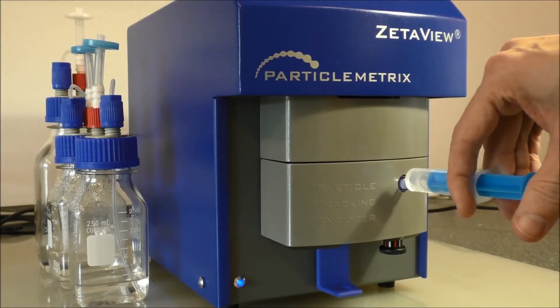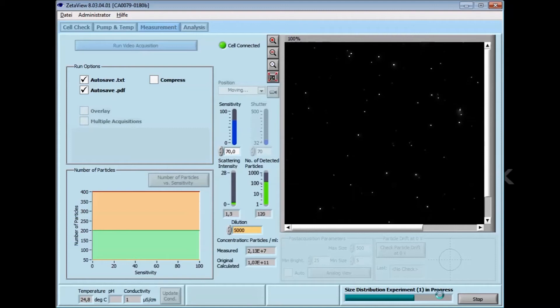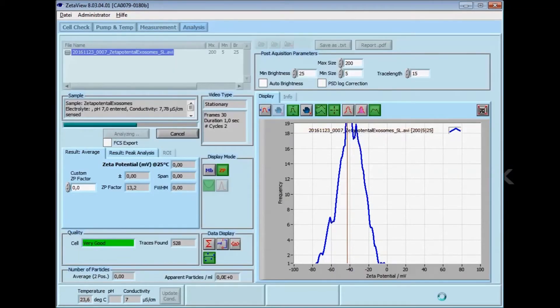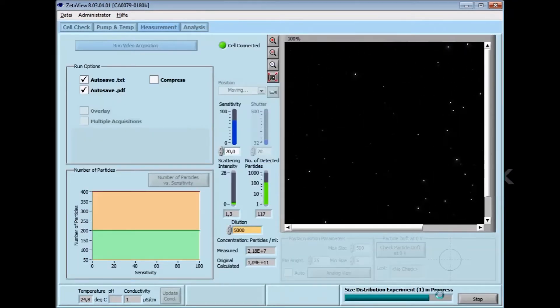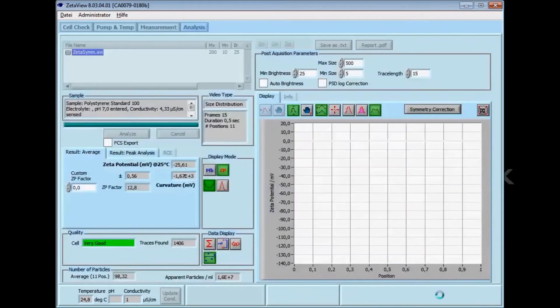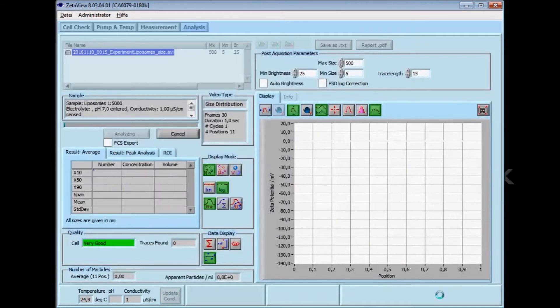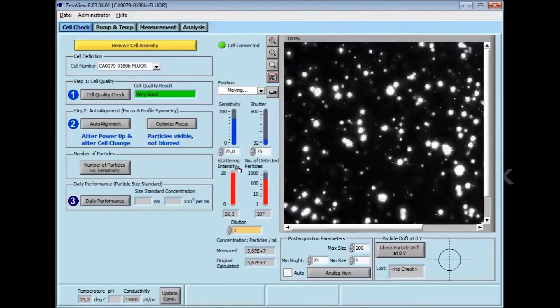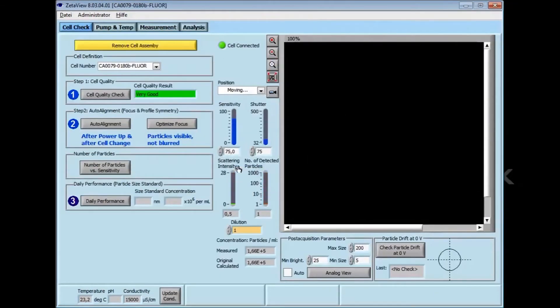The ZetaView is a next-generation nanoparticle tracking analyzer that measures hydrodynamic particle size, zeta potential, and concentration through the analysis of a video sequence at 11 separate positions in the flow cell. Each individual particle in the three nanoliter field of view is counted and tracked in short video clips, creating accurate concentration calculations and particle size distributions. The ZetaView combines these Brownian motion measurements with classical microelectrophoresis to determine zeta potential.